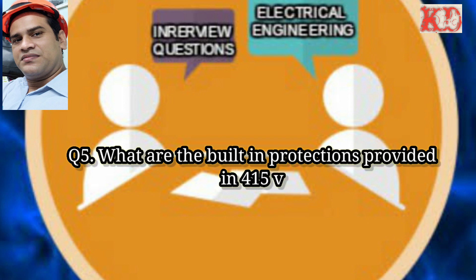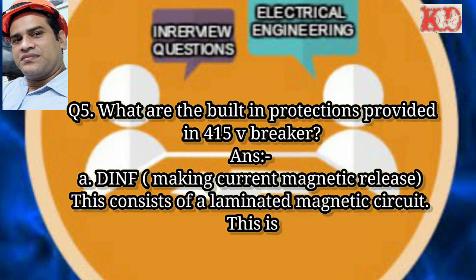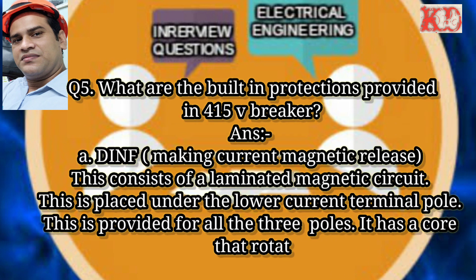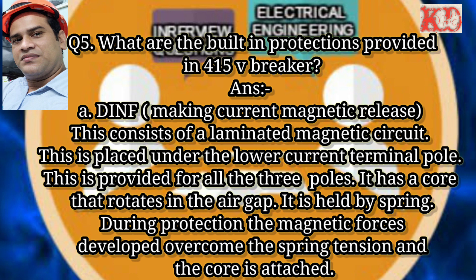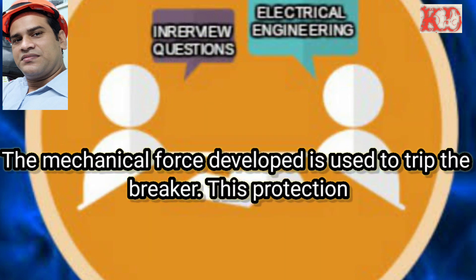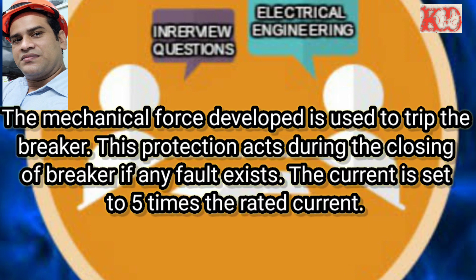Question number five: what are the built-in protections provided in a 415V breaker? Answer — first, DINF: DINF is making current magnetic release. This consists of a laminated magnetic circuit placed under the lower current terminal pole, provided for all three poles. It has a core that rotates in the air gap, held by a spring. The magnetic forces developed overcome the spring tension, and the core is actuated. The mechanical force developed is used to trip the breaker. This protection acts during the closing of the breaker if any fault exists. The current is set to five times the rated current.